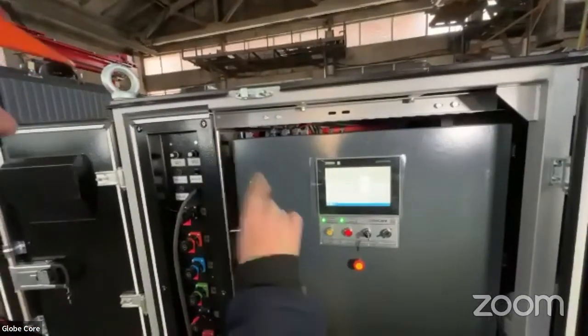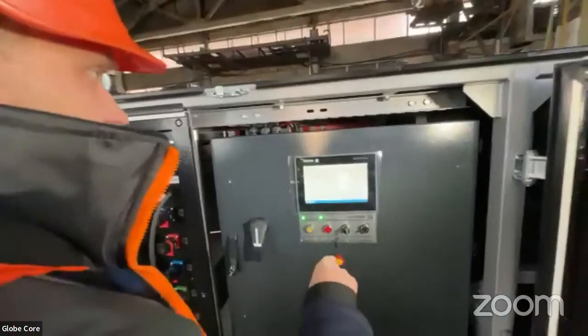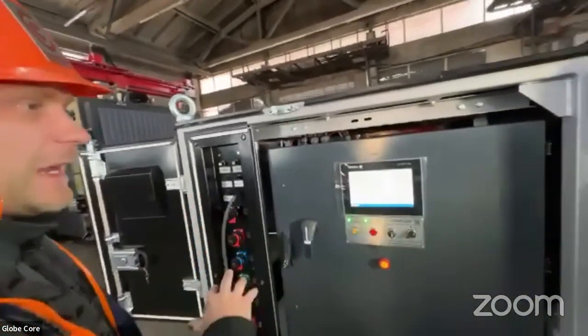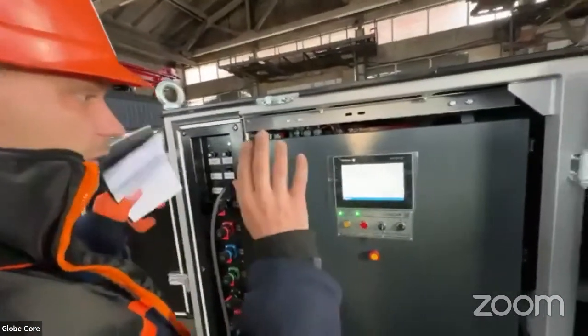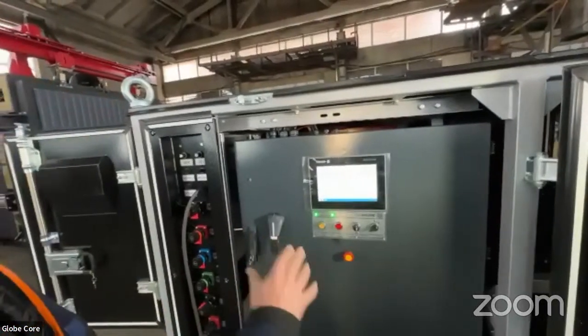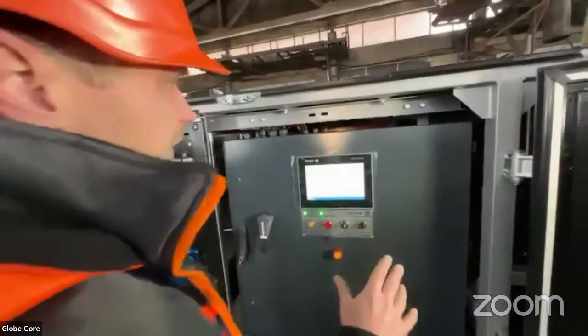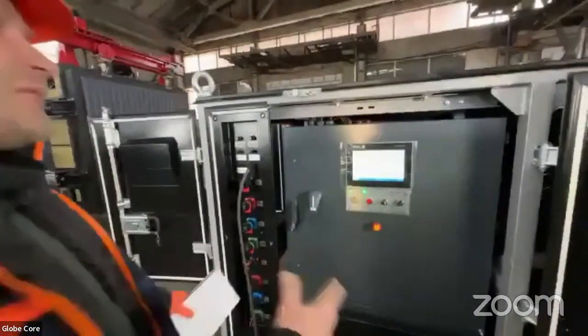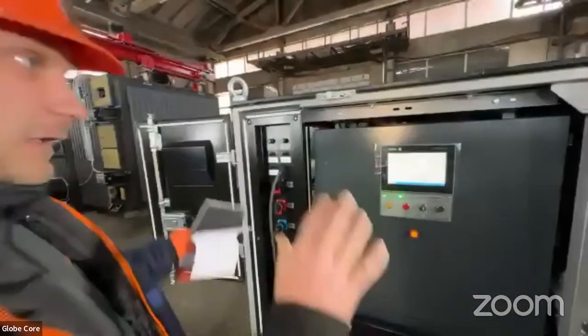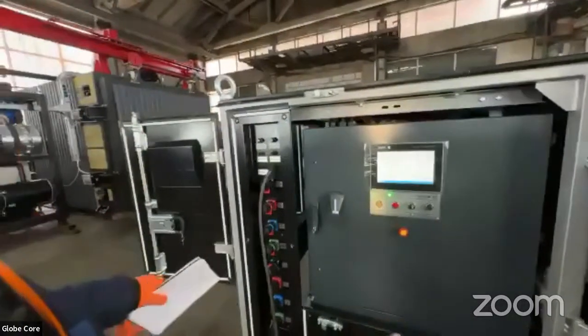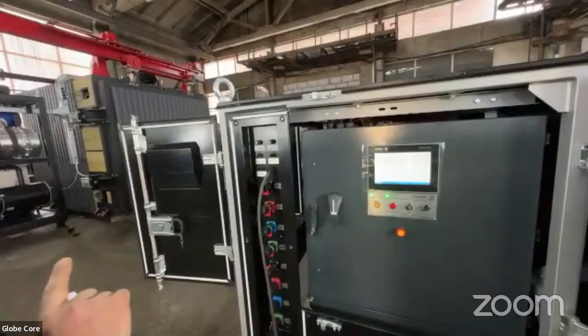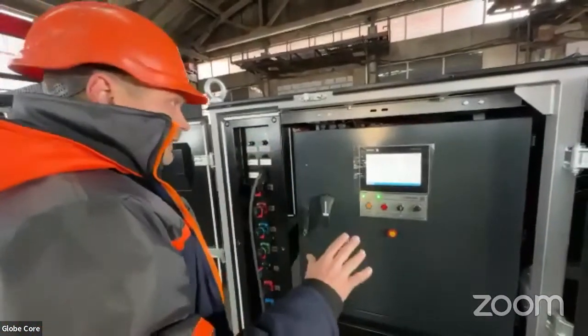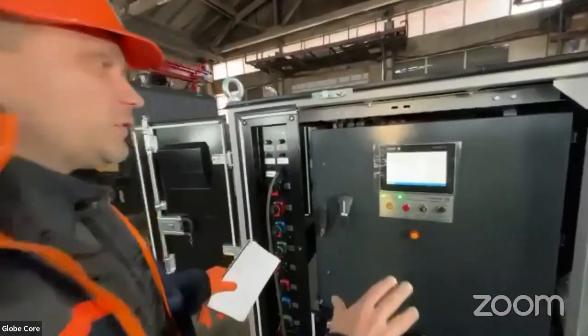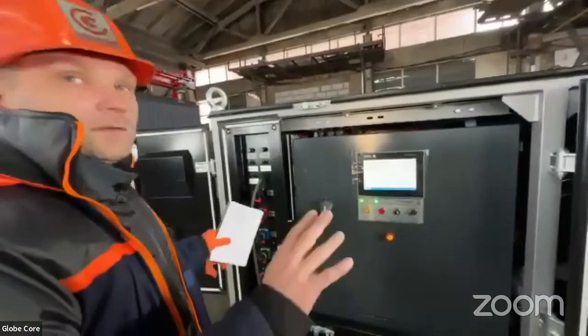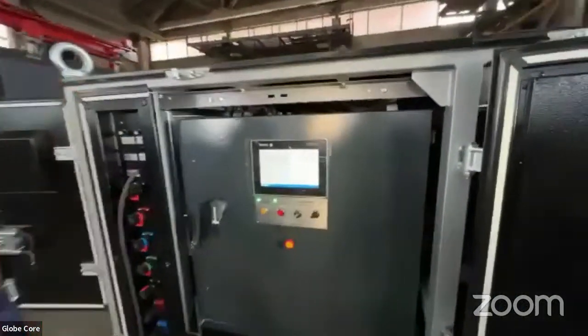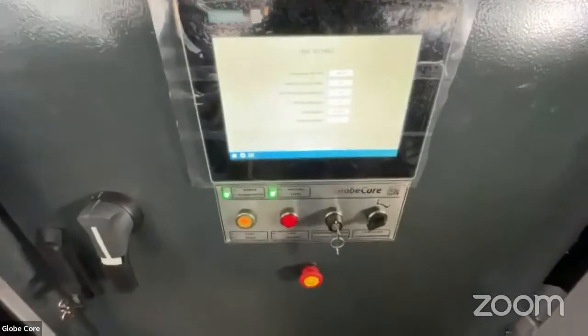So particularly this LFH module is supposed to work with the client's vacuum system. So low frequency heater provides the heating of the windings, and the vacuum system of the client provides the removing of extracted moisture. Once again, this unit is supposed to work with the client's vacuum system. Just to say that the system also can be used in combination with an oil drying unit. And this coefficient is dependent on the type of combination.